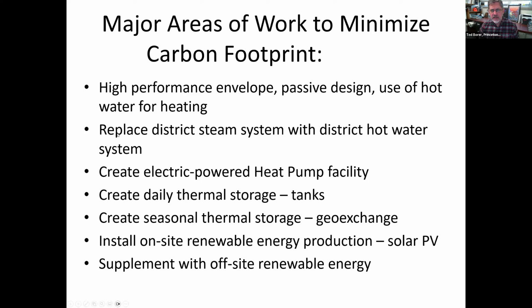It may involve windows, air sealing, insulation, or HVAC scheduling. We're replacing the district steam system with district hot water. Like the other speakers, this is a non-trivial project. We're putting 13 miles of district hot water system in a campus where we've been burying utilities for 270 years, so there's a lot of stuff on the ground to be avoided. The only place we can't put the new hot water system is where the steam system is, because everybody in that building wants continuous hot water. So I need the hot water working before I can remove the steam line.